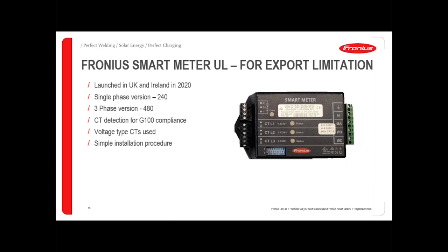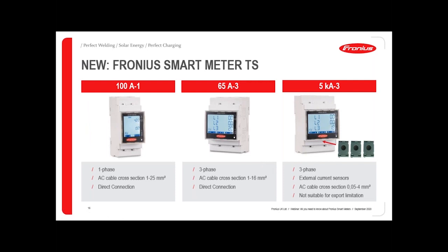I find this meter much easier to install because you simply look at the LEDs on the front of the meter to check that you have a good connection with the CTs, and the addressing is done using the DIP switches on the front of the device. We also have a new range of touchscreen smart meters — we're calling these the TS range. I want to really focus on the 100 amp meter, which is particularly useful for UK and Ireland where we have single-phase installations with up to 100 amp supply and 25 millimetre cross-sectional area cables for the incoming cables. We now have terminals on this meter that mean you can directly connect this after your main breaker within a building.